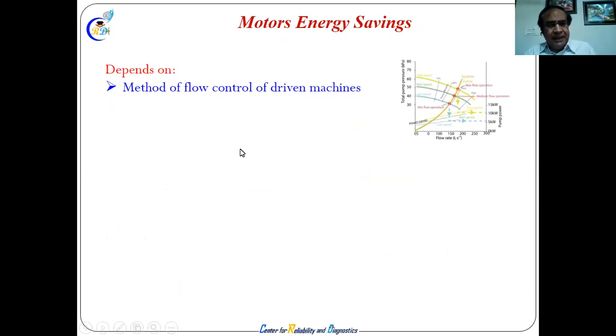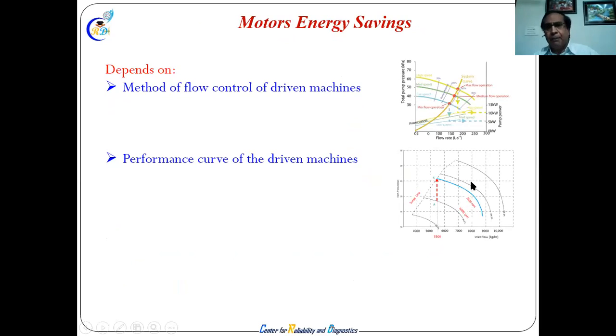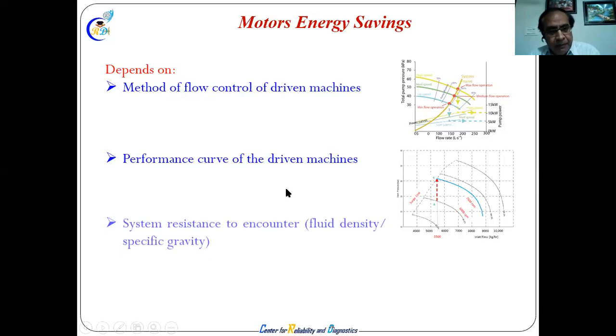So it depends, there are many things, on flow control and energy saving, which we have discussed in pumps also, on the last page, for whoever attended. So there is flow control. You can control the flow, you can save the energy. Okay, performance curves of the driven machine, all the driven machines, pump, compressor, anywhere, for all the energy savings, how the performance of the driven machine is, that is the ultimate criterion for energy more or less in the driver. If the driver is the motor, then the driver motor has to take into consideration the driven machine's behavior. That means its pressure, flow, temperature, vibration, all the things have to be taken care of. So that is what the performance curve of the driven machine means.